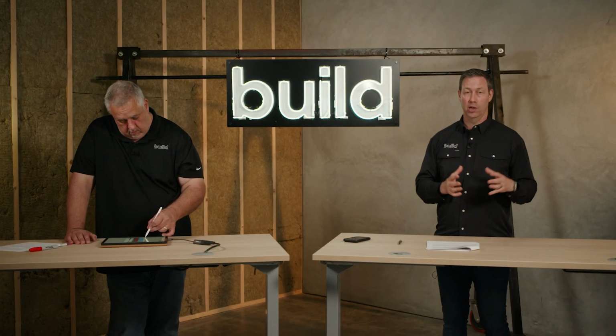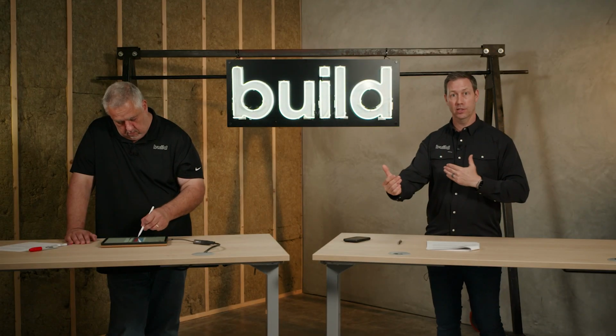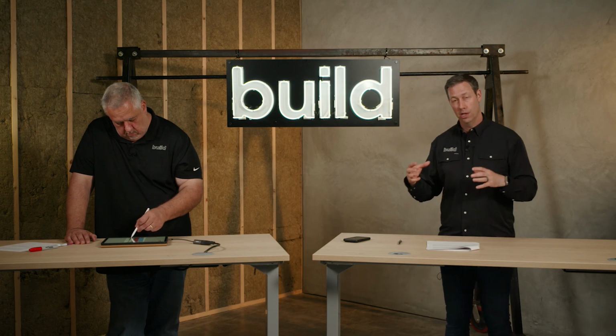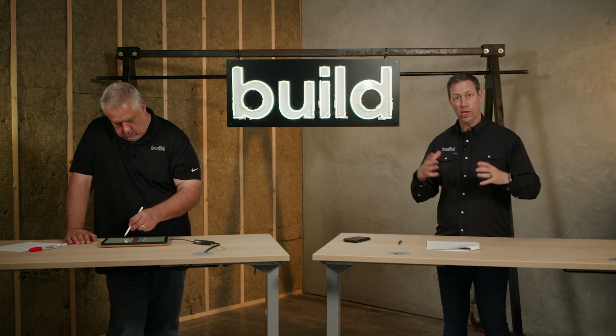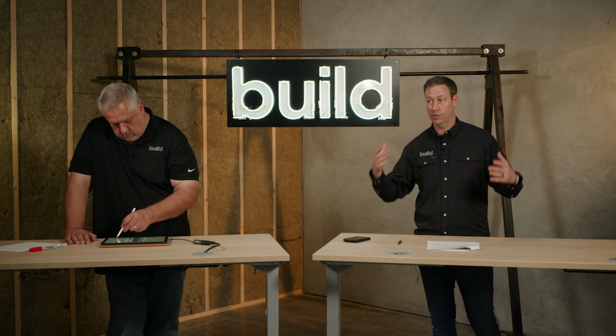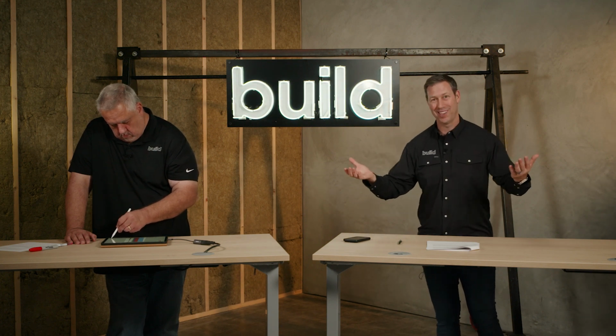An analogy I like on this, if you'll permit me, is thinking about a blower door. That's this big, sometimes red door that you take out the front door, you put this in, and it's got a fan that's calibrated, and you use this thing called a manometer, which is able to measure pressure differences, and you pressurize the house to a certain number. It's a Pascal rating. We're trying to get a difference between the outside and the inside of 50 pascals. And because the fan is calibrated, we're able to figure out how leaky the house is. In other words, how big is the opening on the window that you can't close.